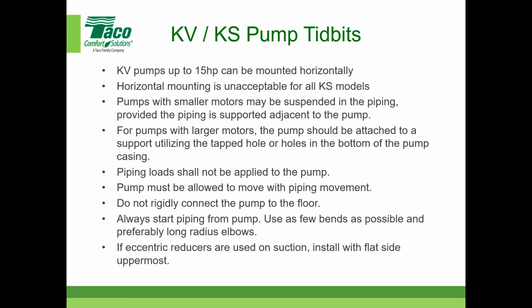I like to hit this home again: if you're using eccentric reducers, which are used a lot, on the suction, install the flat side uppermost. It helps the flow get into the pump, if you look at the casing and whatnot.